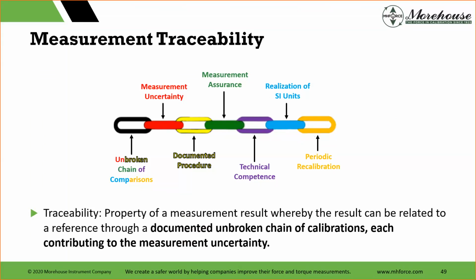So if you start with Morehouse, we calibrate your device, our machine's 0.025%, you have to absorb our uncertainty. Then if you use your torsion cell to calibrate another torsion cell, you do all the stuff. You calculate your measurement uncertainty in accordance with ILAC P14, A2LA guidelines, everything else. The important thing is you cannot have an uncertainty better than what we have. And then it's just going to keep getting propagated and larger and larger.